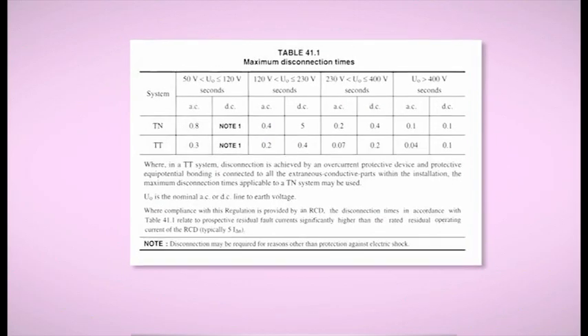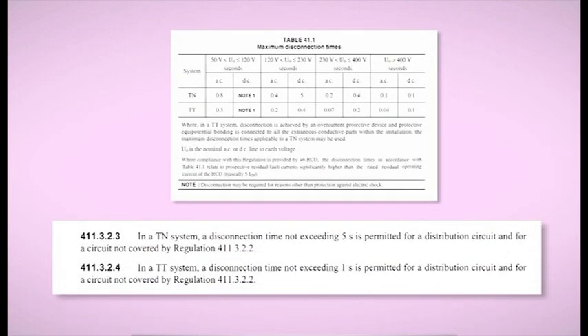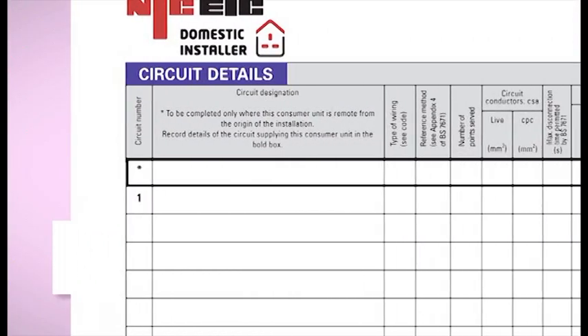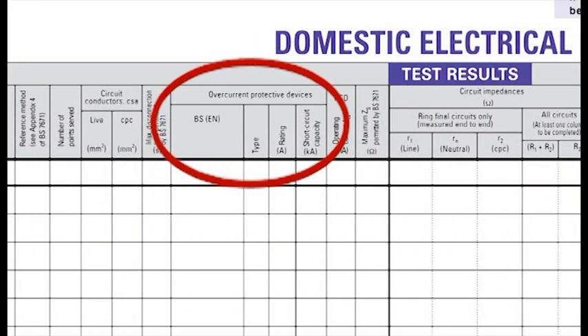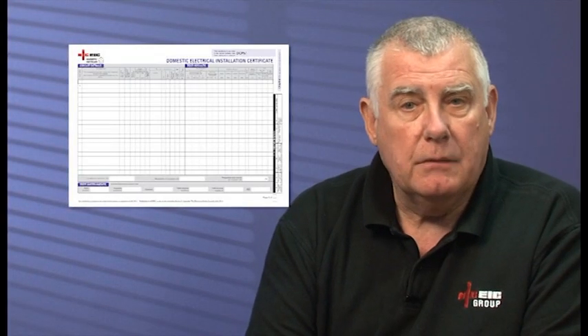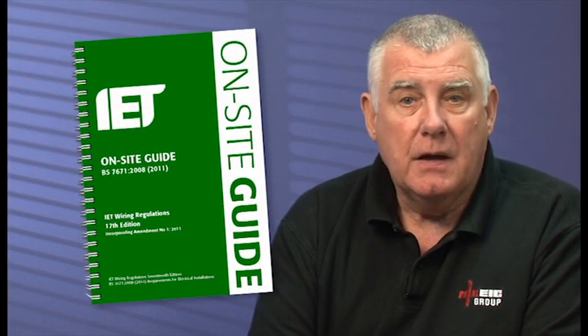For circuits exceeding 32 amps or distribution circuits, the disconnection time can be extended to 5 seconds and 1 second respectively. The next 4 columns deal with the details of the overcurrent protective device for each circuit. For circuit breakers, this information can be taken from the device, just as we did for the main switch. However, where not available, you may have to consult the manufacturer or refer to other published guidance, such as the on-site guide. The capacity is referring to the breaking capacity, so the current which the device can interrupt safely.